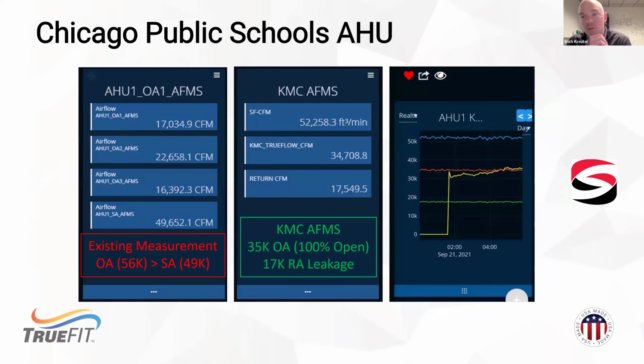So what that means for the school is that when we fired up our AFMS and characterized their system with that characterized airflow performance, and based on the temperatures, which don't lie, we found that at 100% outdoor air damper position, we're only getting about 35,000 CFM of OA. 17,000 is leakage through a return path of every kind. What that means to that school is they're under ventilating by a third from where they thought. Again, in the era of high performance buildings and COVID mitigation, infectious disease mitigation, that's a big deal to be under ventilating by that much.